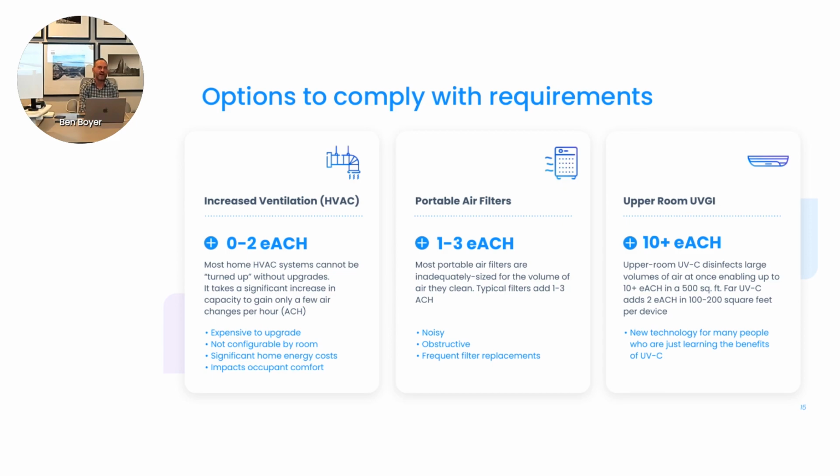Most of our customers have had portable filters. I would say the vast preponderance don't use them anymore. And the reason why they're not utilizing them is sound. They're very noisy if you run those things as they're supposed to be. And so classrooms in particular, it's been a real issue for student learning. There are some classrooms that have multiple filters, or at least try to implement that to get some additional EACH. And the reality is it just wasn't working as it pertains to student learning.